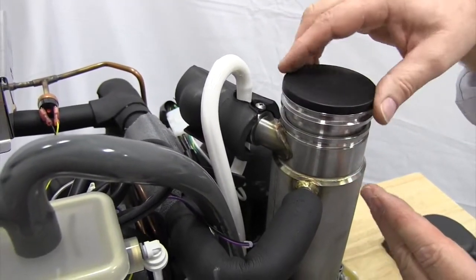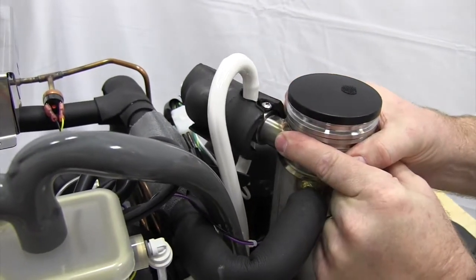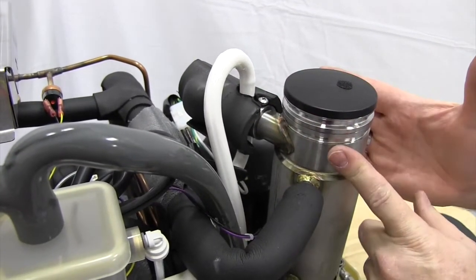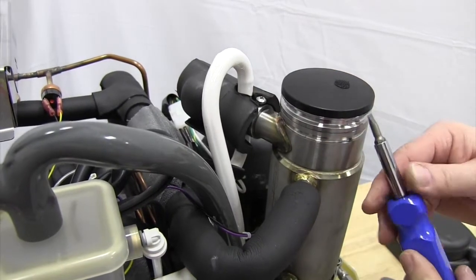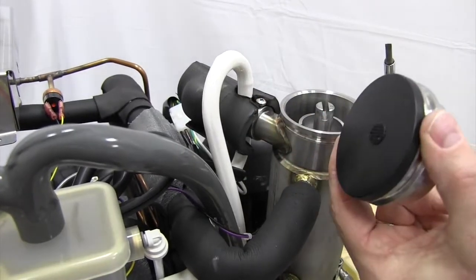So if you do have a stuck bearing on the top, number one, make sure that the machine is at room temperature. When the evaporator is cold, it's going to be squeezing the top of the bearing. So room temperature, and then tap on the upper ring around the perimeter to work the bearing off.